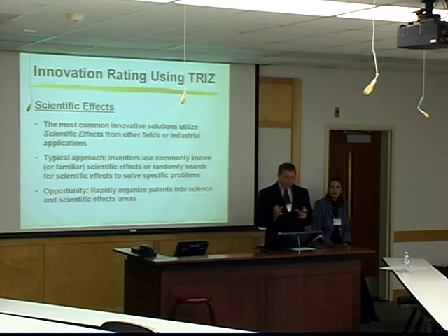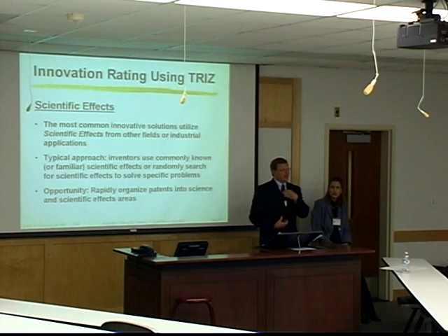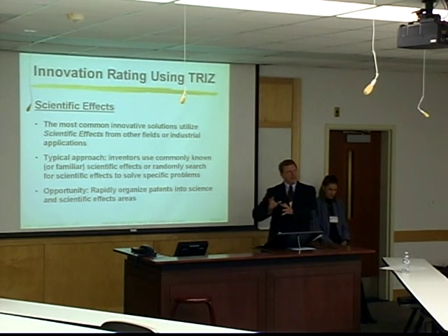So what this medical device company actually developed was they took advantage of the scientific effect. At low temperature, the diameter of this metal support was the diameter of a pencil. It could be deployed into the body and, when actually deployed from its shield into the area of the aorta, this nitinol, the shape memory metal, would expand to the diameter of a quarter. It made a rigid support at the top and the bottom, so it didn't move.